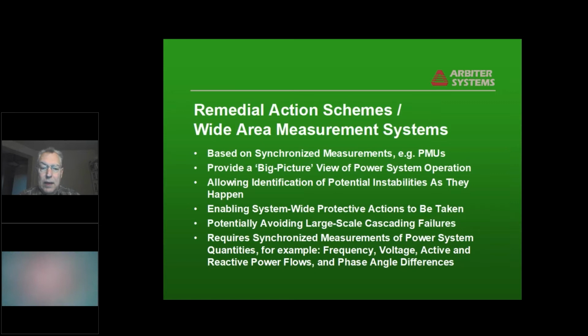Remedial action schemes and wide area measurement, as I mentioned, they use PMUs for that, and as opposed to looking at things on an asset by asset operation basis, it provides a big picture view of the whole power system, and it allows the utility to identify problems, typically potential instabilities due to some combination of assets being down for maintenance or because of a fault. And if the system is getting to the point where the stress levels are running the risk of taking the system down, system-wide protection actions could be taken by selective load shedding or turning on a backup generator or whatever to avoid large-scale cascading failures.